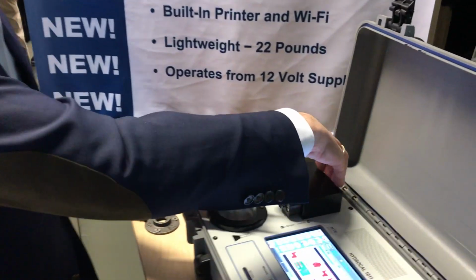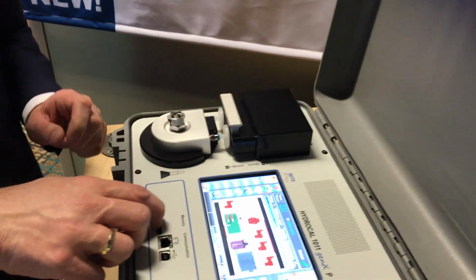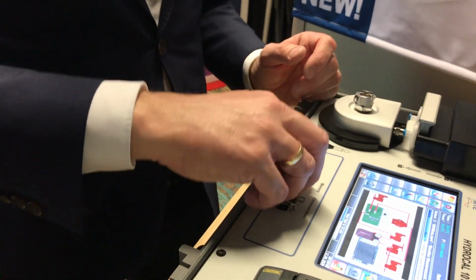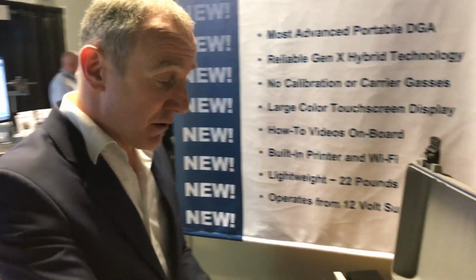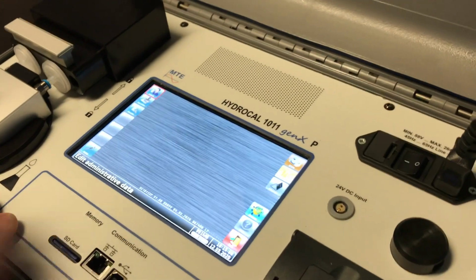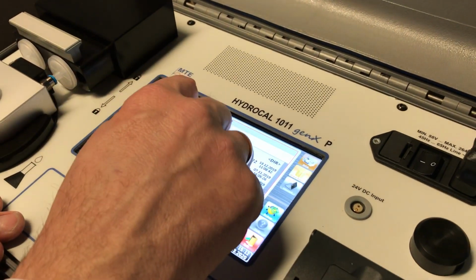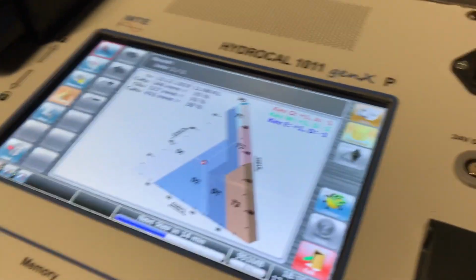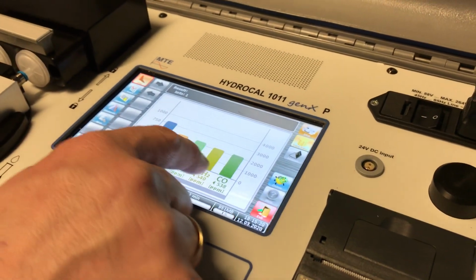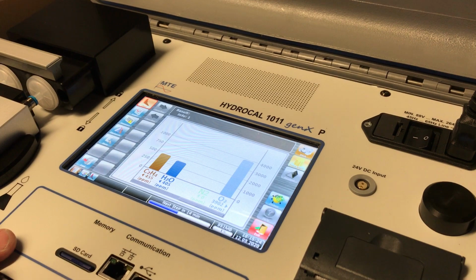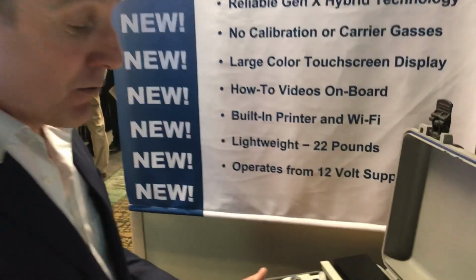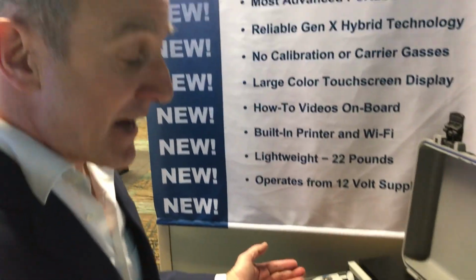Other advantages of the H1011 Gen XP is that it is equipped with an SD memory which can record thousands of data sets. That means the same transformer can be tested in regular intervals, and the device is showing then the trend of the dissolved gases. The device is also able to show, for example, the Duval triangle after an analysis of the oil, or to show all the different gases, including their contribution.